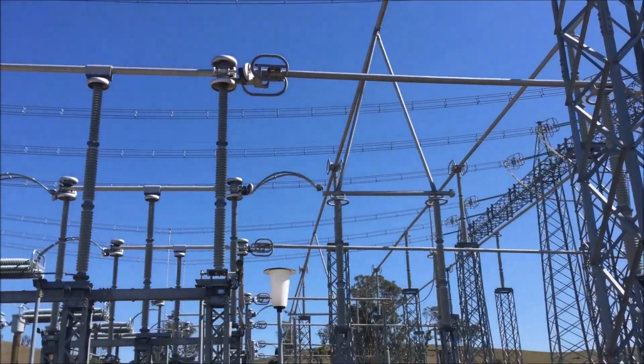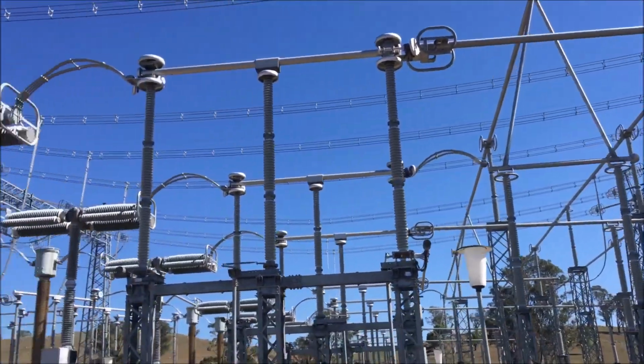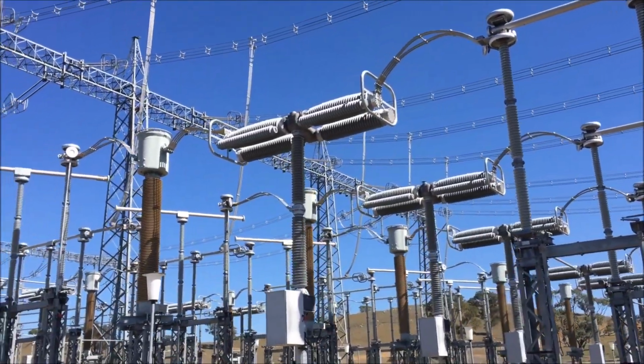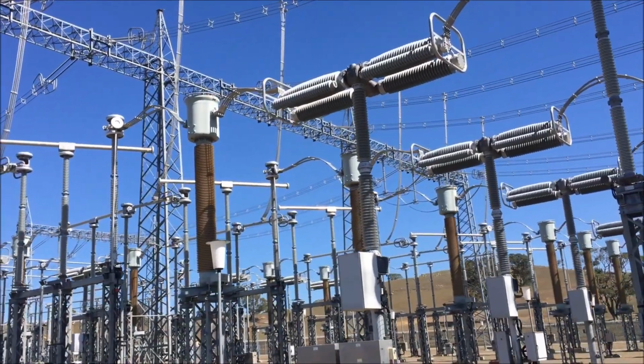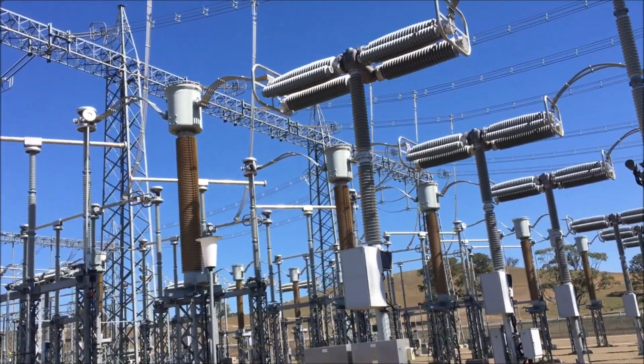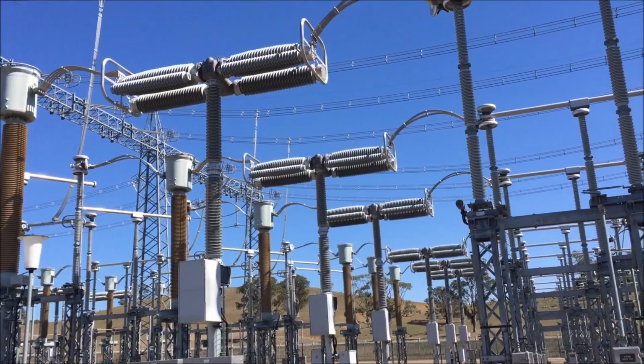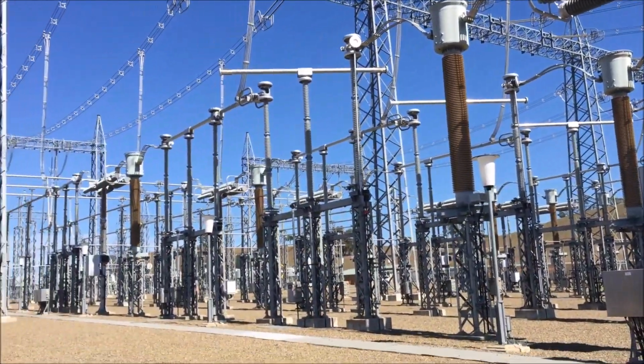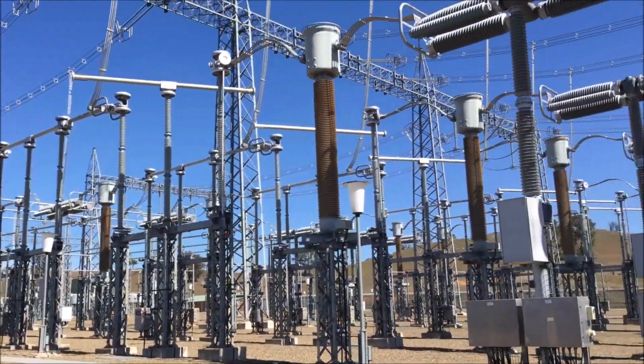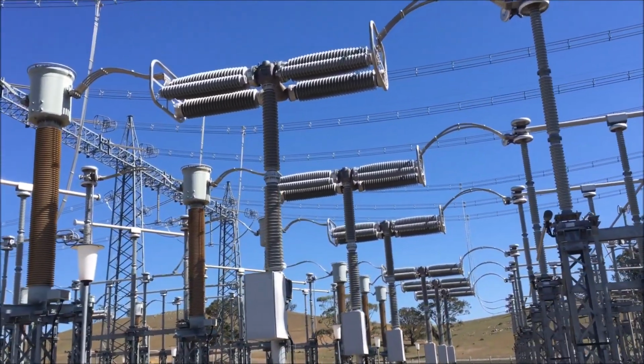Yeah, it comes in onto the bus bar. The substation is a mesh arrangement. It needs only 4 circuit breakers. With that you can isolate either line or either of the two transformers in the substation.